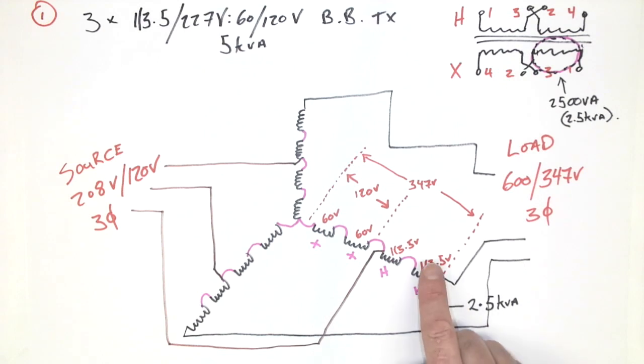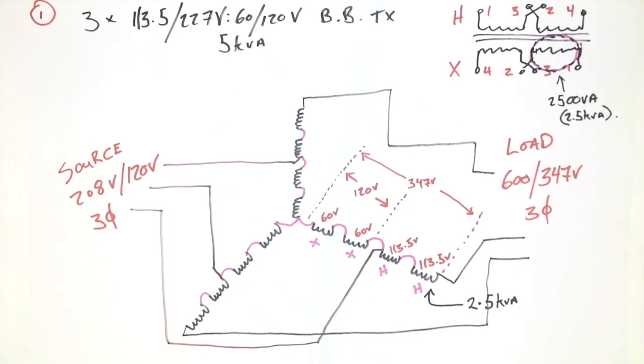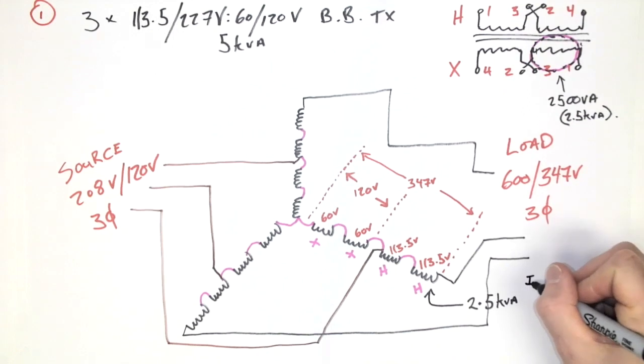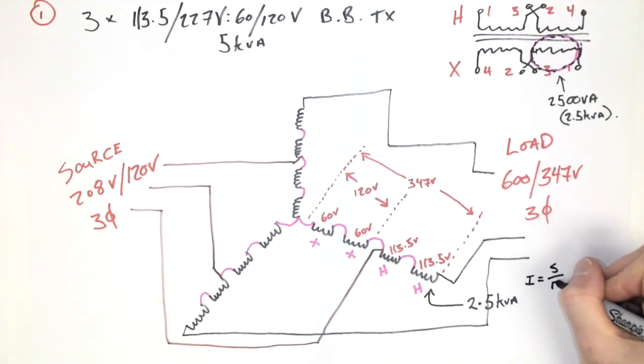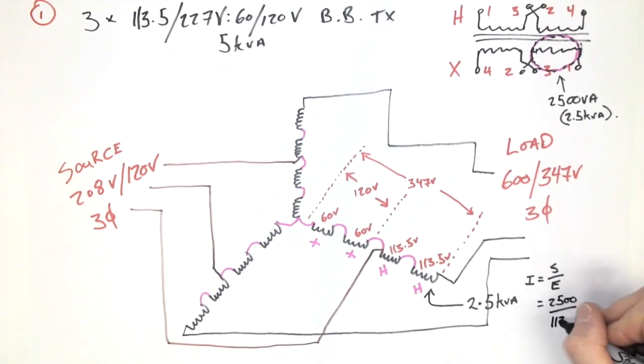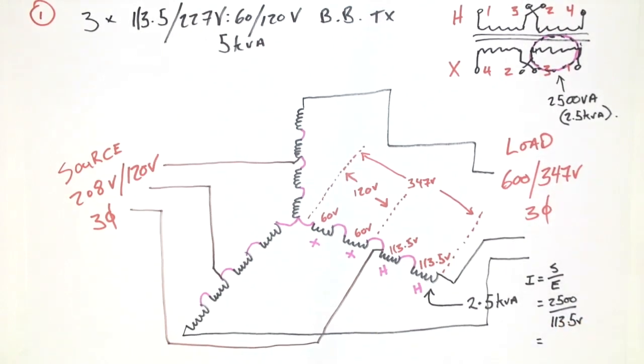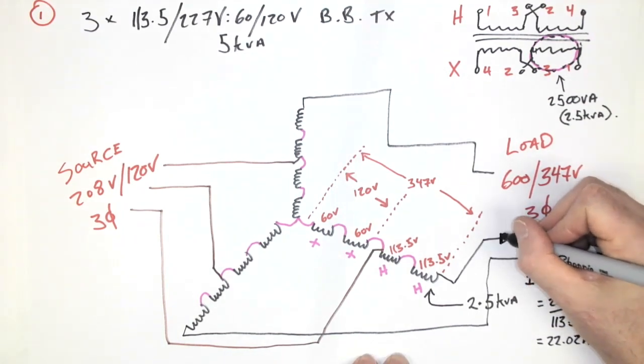The VA is 2.5 kVA, the voltage is 113.5. So all I'm going to do here is a very simple single phase calculation. I is equal to S over E, 2500 divided by 113.5 volts. What this gives me is a current value. This is the maximum current that this particular winding in the transformer bank can handle, and it comes out to 22.02 amps.